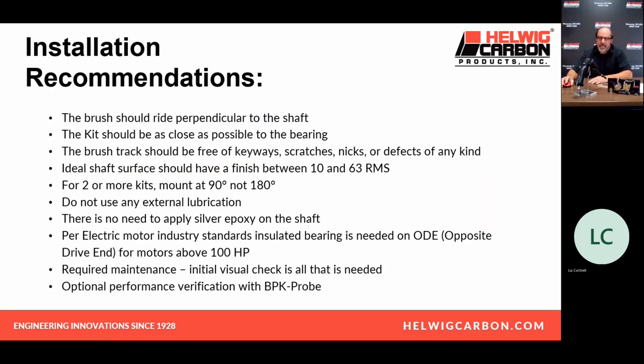Installation recommendations, these are about the same as everything. I'm not going to go into too much detail on here. Make sure that our kit is properly installed, which means making sure that it's on the motor shaft, properly spaced. We give you the little gauge to make sure that it is, and the shaft starts clean. You have to start with a decent shaft for us and put it on, walk away.